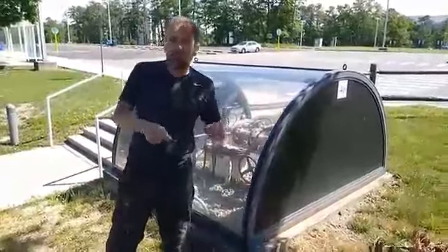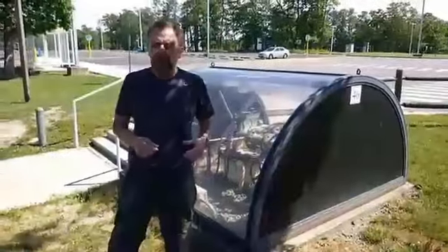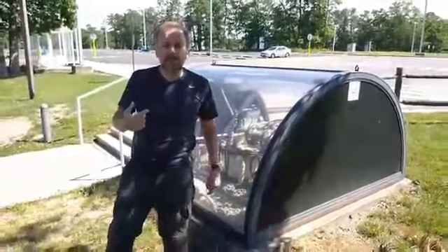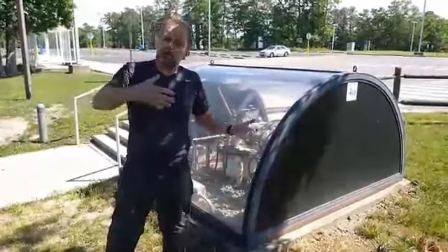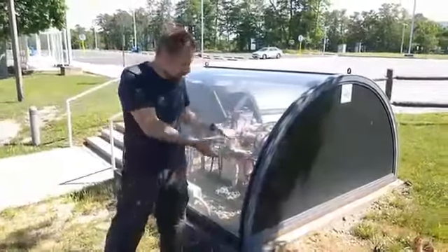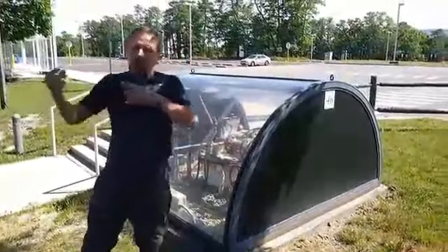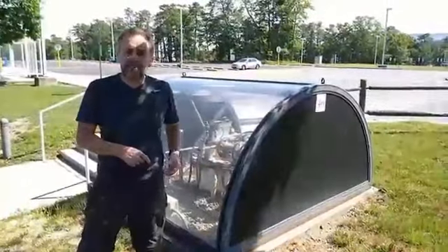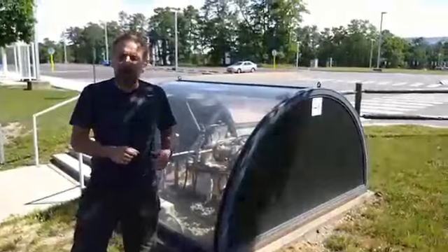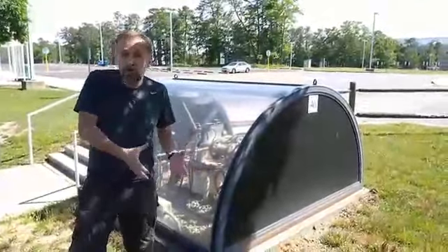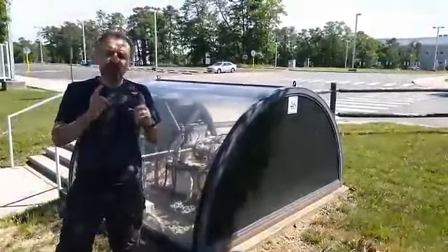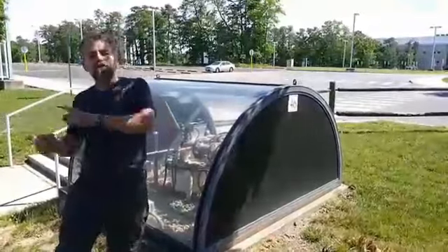And it turns out here, because there's not much movement, we're able to get back over 90% of the cold that we put in the ground. So we suck up water, cool it down, put it back in the ground, and six months later, 90% of that winter cold we've stored in the ground is still available to us. And then we use that to pre-cool the air.